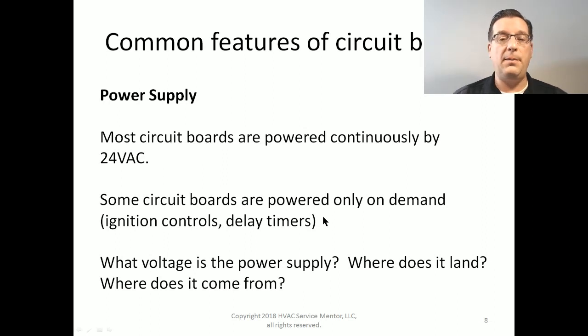Some circuit boards are only powered on demand. And that demand could be things like ignition controllers. The Honeywell S86 series control boards are a great example. Delay timers will be found on condensing units, or on certain boilers for pump operation.